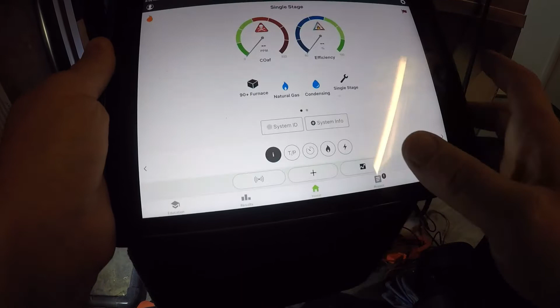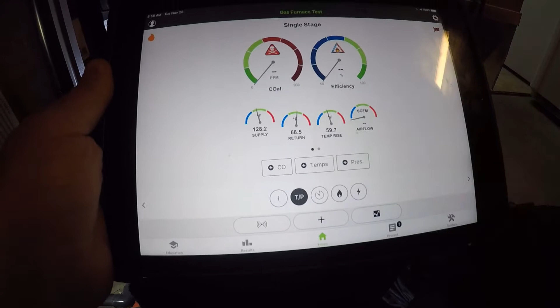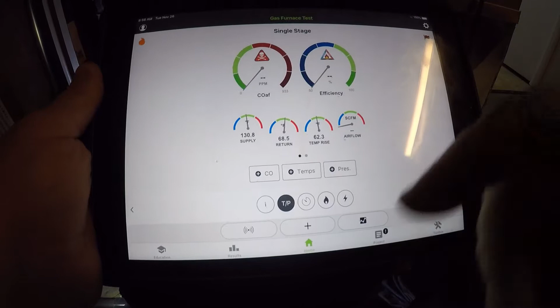And my static is 0.8. So now that I've got everything profiled, ECM motor, all that's done, submit. Everything should be loading up. As you can see, my gas pressure and my temperature rise are coming in. So now that it's profiled, I'm going to put everything together and let it run 5-10 minutes, see how everything's doing.